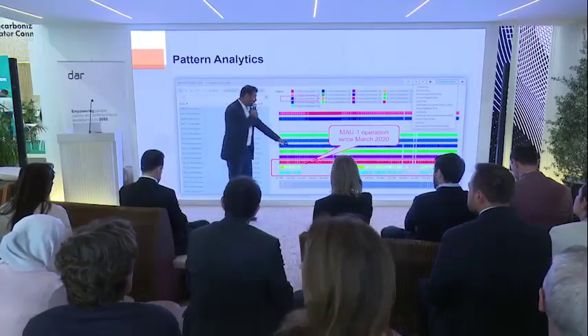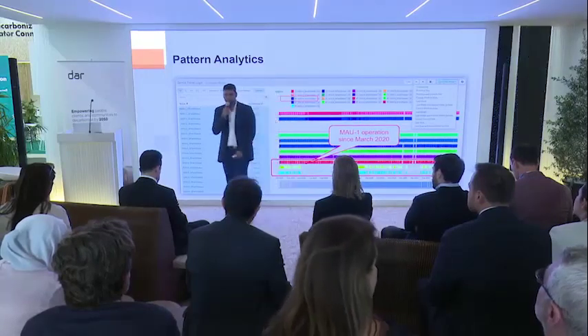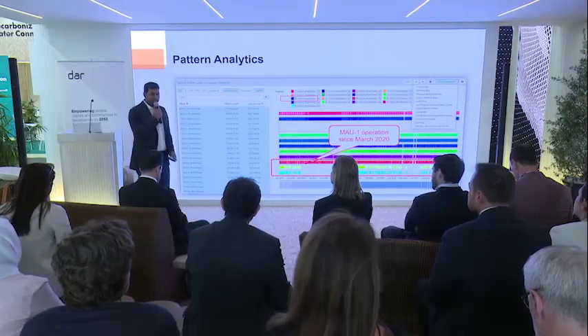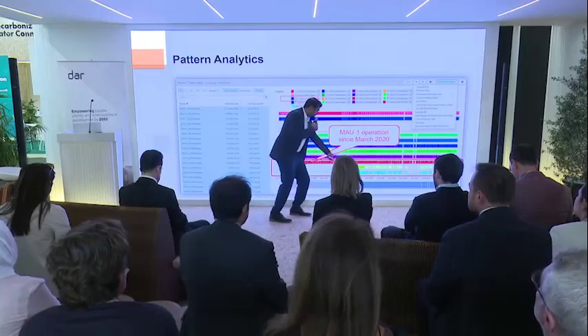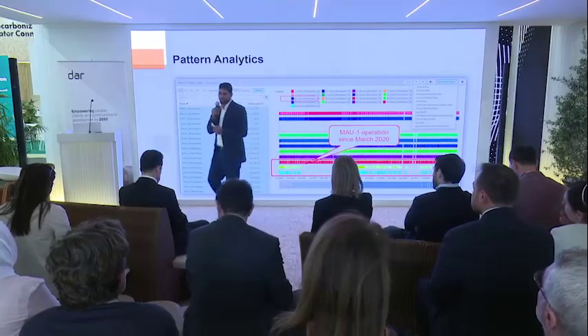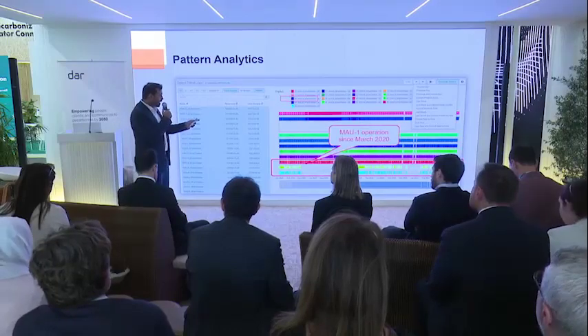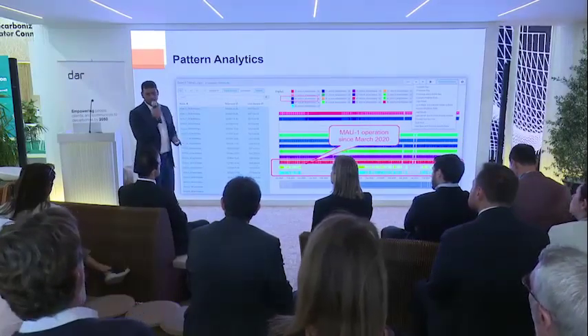What happens in a case like this? In this example, we pulled data sometime in June 2020. We did have the history, and right off the bat, you're able to detect something that's wrong, and then what we are after is this: real changes happening in the building using information that's coming out from the system, where a fan that was running 24/7 now shuts off during the night.